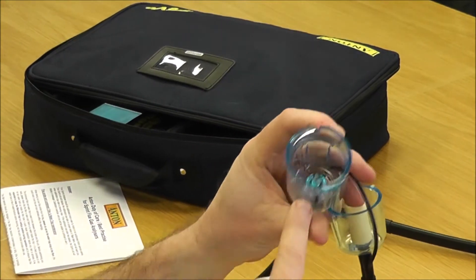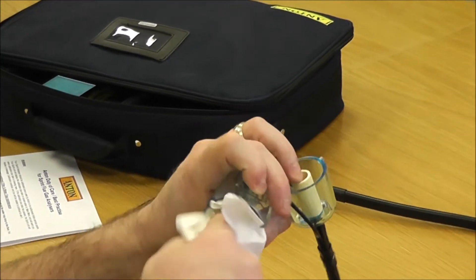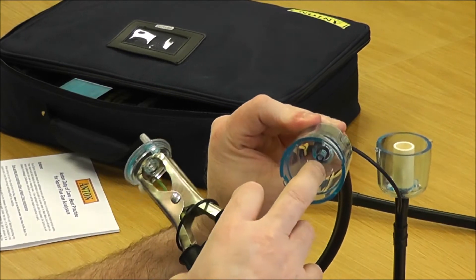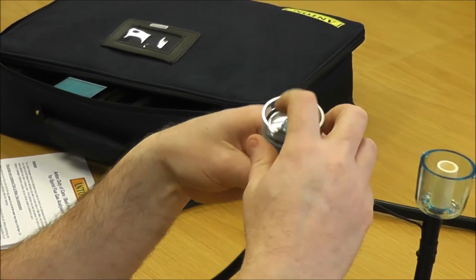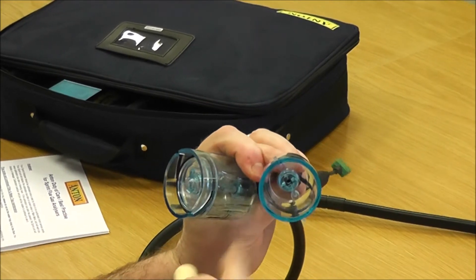When you open it up, if there was any moisture or condensate in there at all, it needs to come out — just dry it out with a dry cloth. Removing the middle disc allows you plenty of room to take all the moisture out. You'll see it's got a spigot pointing up, and inside in the middle there's one looking very similar — that's how I remember which way around they go. Pop the middle disc back on and the O-ring goes on top of that.